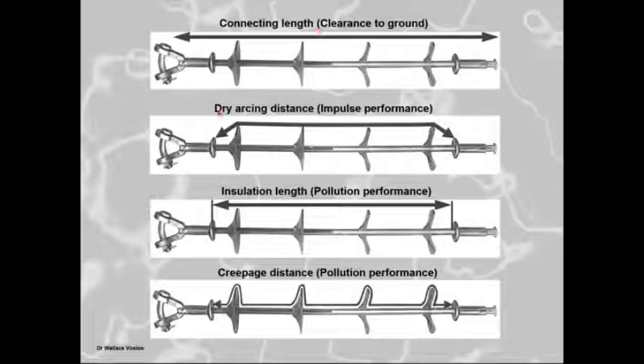Then your dry arcing distance is the shortest distance you can take a piece of rope that does not stretch from the dead end side through the air over the sheds to the closest end metalwork. Now, if there was a corona ring, it will be there.